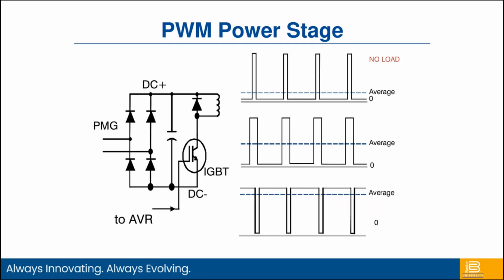However, one of the advantages of many of our digital voltage regulators is that we use a pulse width modulated power stage. We'll talk a little bit about the advantages, but first let's look at how it works. Rather than have the SCRs on the bridge input, like the full wave SCR based stage, we're just putting a diode based bridge here. This diode based bridge is rectifying the AC all into DC and charging this capacitor. We call this the bulk capacitance. It's basically just charging that capacitor to a full high DC output. Then we use an IGBT, or insulated gate bipolar transistor, to create pulses out into the field. Based upon how much excitation we need, we increase or decrease the pulse width and provide the DC to the exciter field.